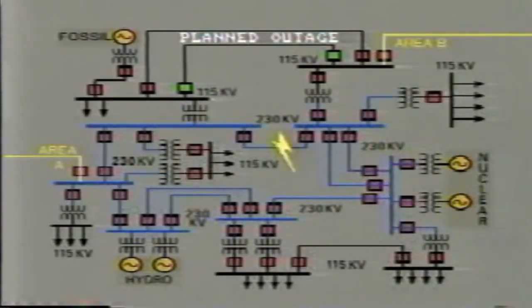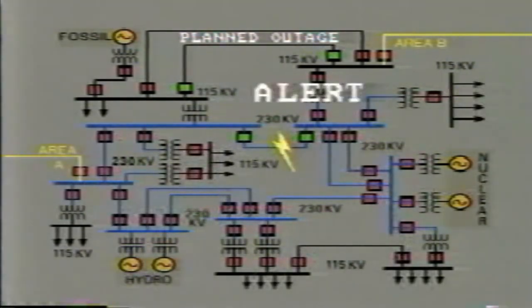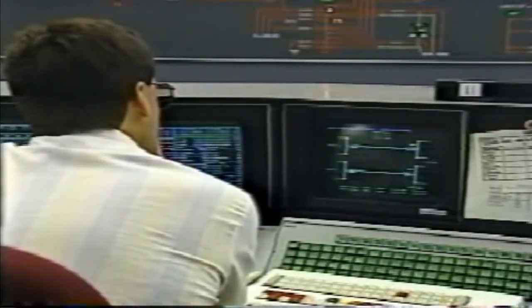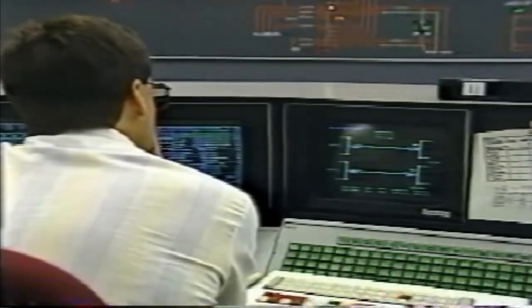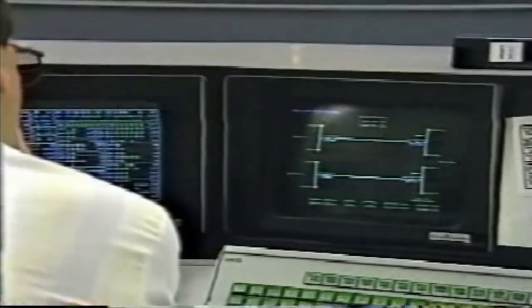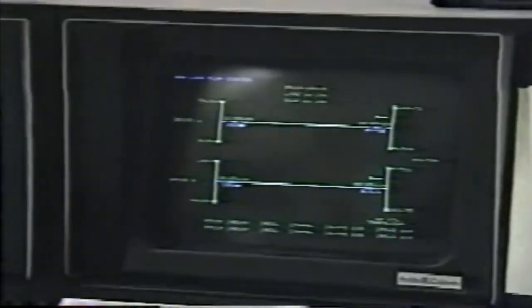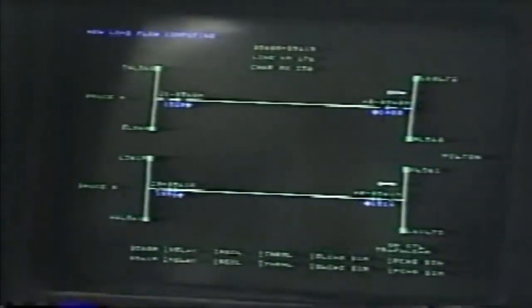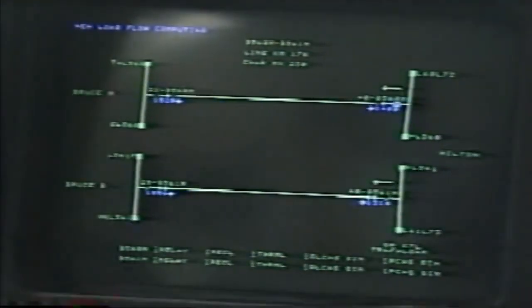However, if a forced outage did actually occur under these conditions, the operator would move to a state of alert, as the system would now be considered abnormal. On most power systems, this one forced outage would not cause an entire system upset. But this abnormal operating condition may leave the system in a weakened state. The system operator will try to place the line back in service as soon as possible, or once again, rearrange the system conditions so as to reduce potential for further problems.